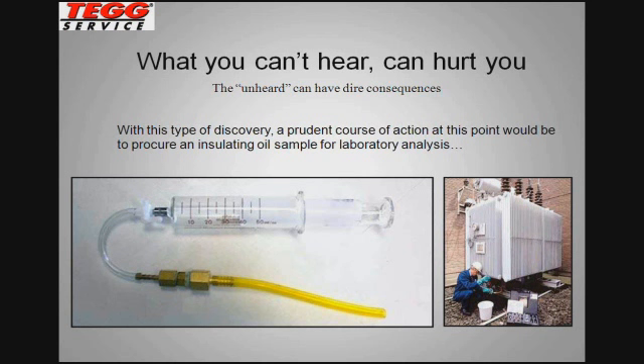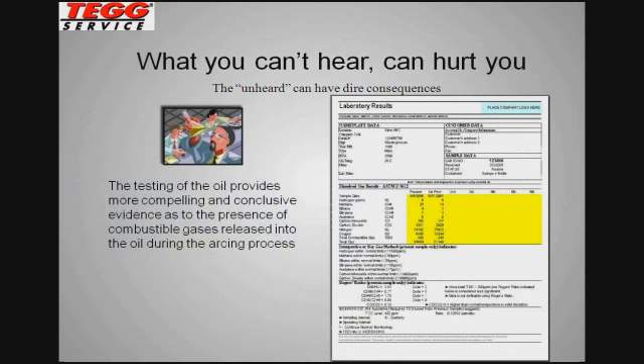in oil analysis. When you have tracking or arcing or corona, be it nuisance or destructive within an oil-filled component, there are certain combustible gases that are released within the oil. And with laboratory analysis, those can be identified to confirm the findings of things like the ultraprobe would indicate. And that was certainly a next step in this particular find.